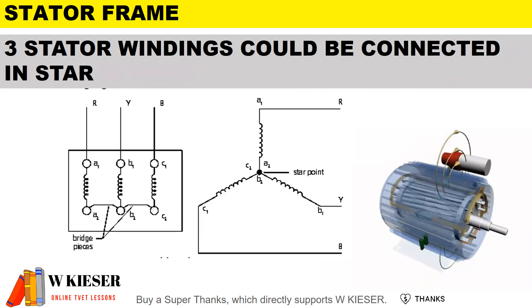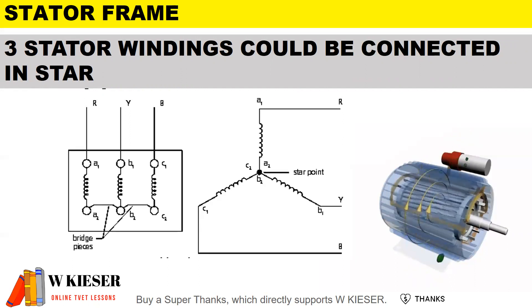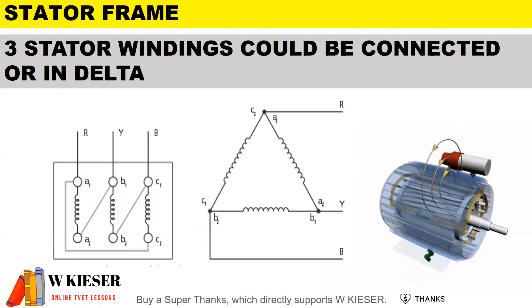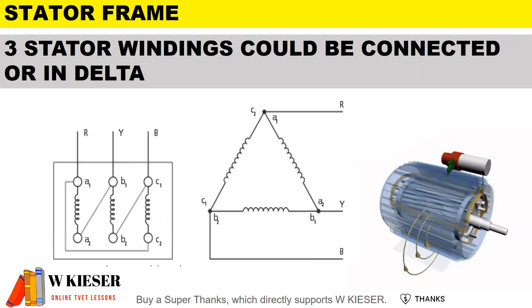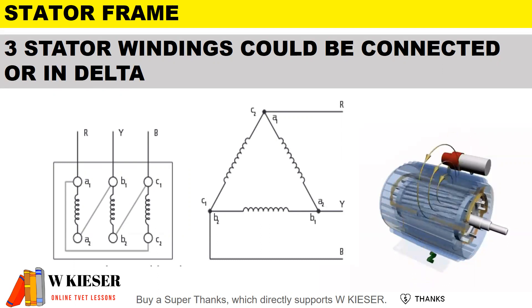The three stator windings could be connected in star. If you have a look at the terminal box, you'll see that for a star-connected three-phase motor it is bridged horizontally. The three stator windings could also be connected in delta. If you look at the terminal box, you'll see that the stator windings are bridged vertically.